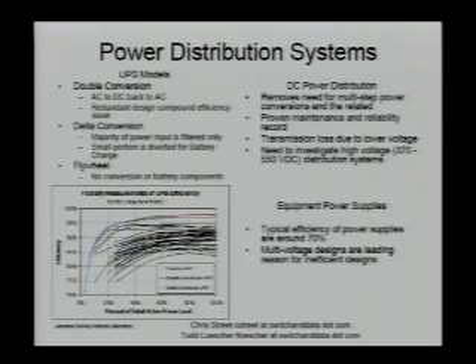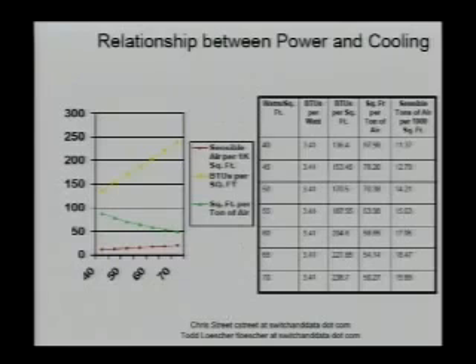The third major component of inefficiency in data centers is in the power supplies for the equipment itself, based on the multi-voltage regulation within the power supplies or component systems. You'll see anything from 1 to 12 volts. By reducing or eliminating that, getting to a standard voltage across the entire system, you'd be able to take out the inefficiency from that particular step in the process.